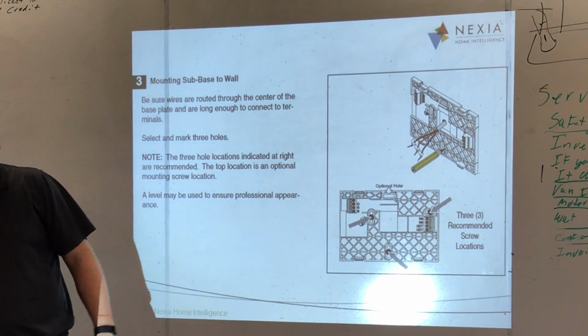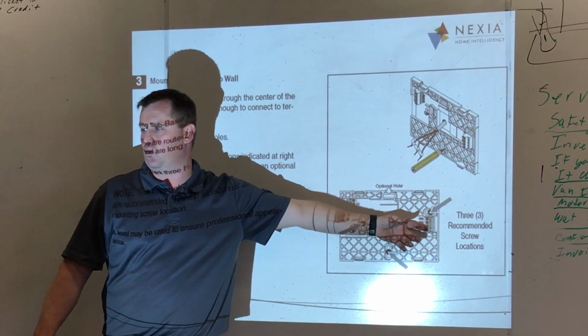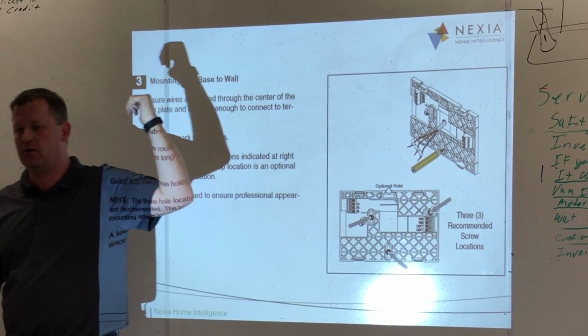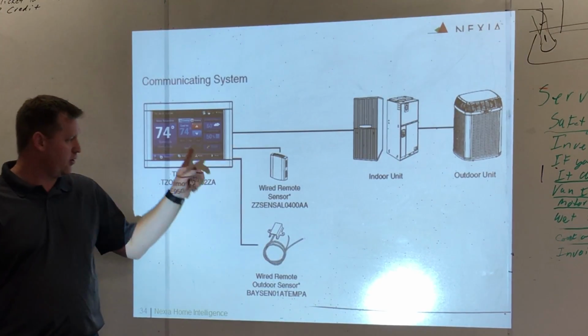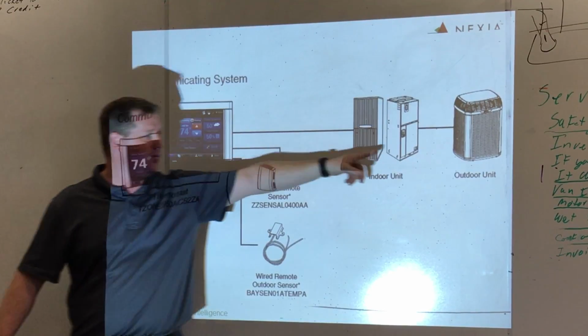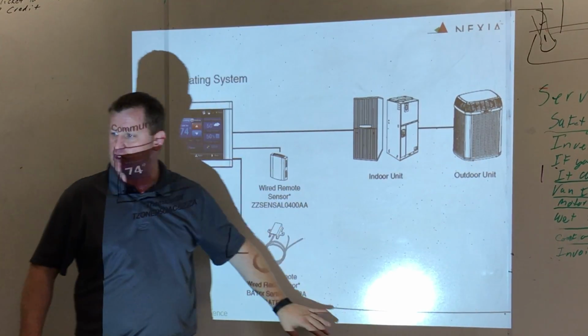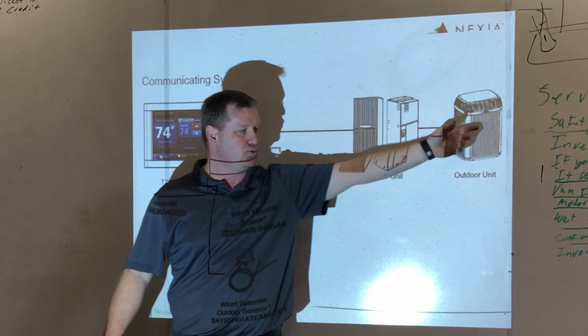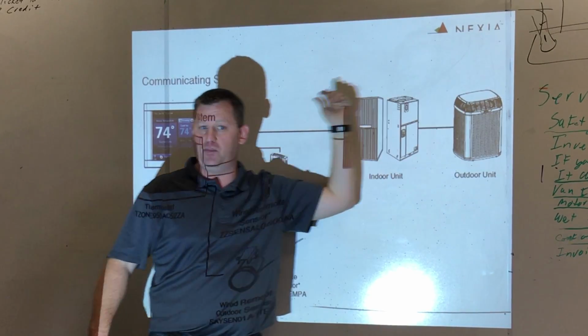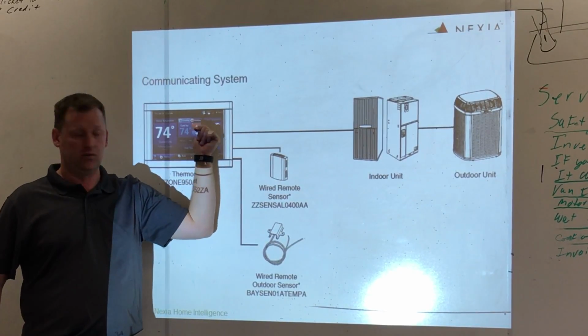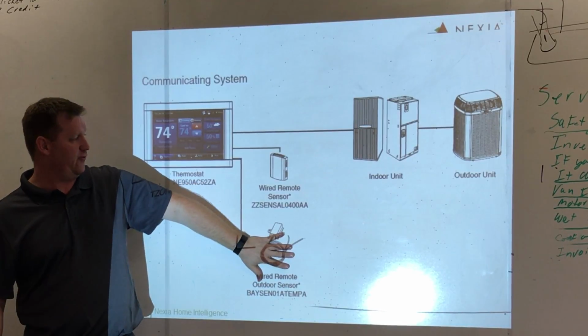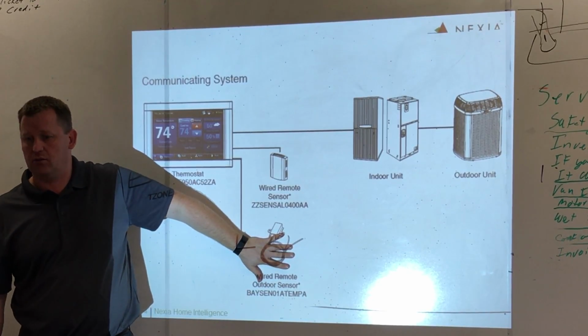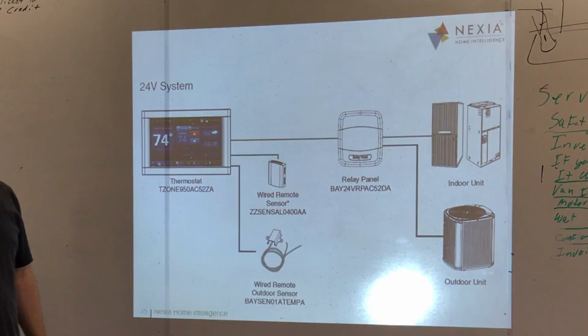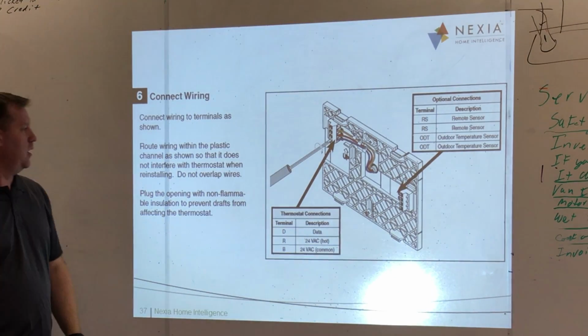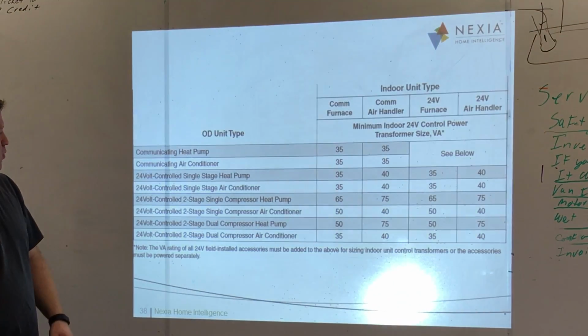Okay? And of course, outdoor sense, remote sense wires here or at the relay panel, right? Also remember, let me back up just a second here. This shows an outdoor sensor going to the stat. If you're communicating equipment, you don't need the outdoor sensor. So ignore that, because we use the outdoor sensor in the communicating equipment for the stat's outdoor sensor. So this is not even really optional. Don't even do it. Okay, ignore that. All right, like I said, ignore the top one.